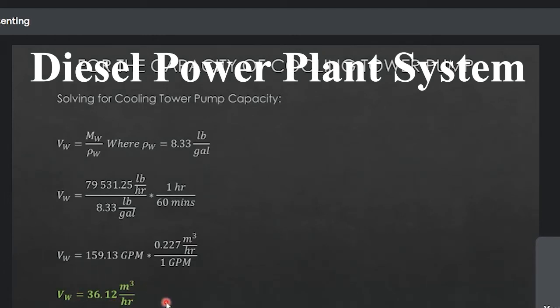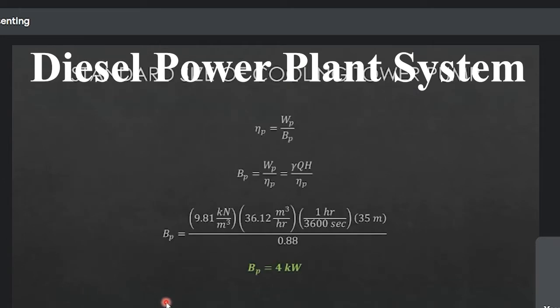Ito yun. So the last requirement would be the standard size of cooling tower pump. Alam naman natin na ang formula for the efficiency ng pump is equal to the output or yung water power divided by the brake power. Since brake power yung hinahanap natin, cross-multiply lang natin ito: yung water power natin would be divided by the efficiency of the pump.